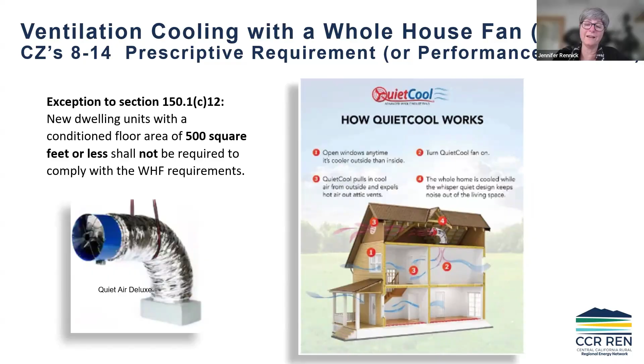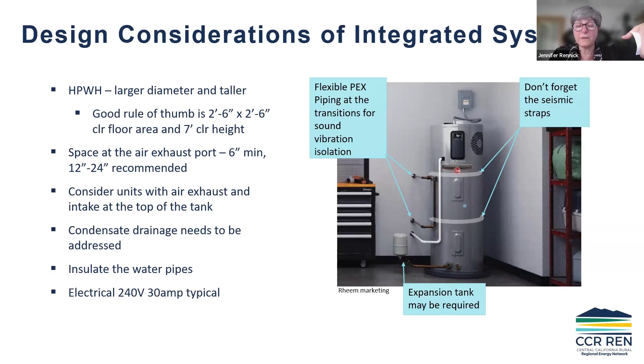Now, last, the heat pumps for domestic hot water. We could teach a whole class on just these heat pumps, but this is the new baseline. There are some new mandatory measures in the code now, and you're going to find it in section 110.3. And then there's a bunch of design considerations for how to design for these. Garages that don't freeze are great because you have plenty of space, plenty of air volume, etc. There are a few things you need to worry about, like the condensate line, and they do exhaust cold air. They pull air in through the top of the unit typically, and then they exhaust cold air after they've pulled the heat out of the air and put that heat into your water.